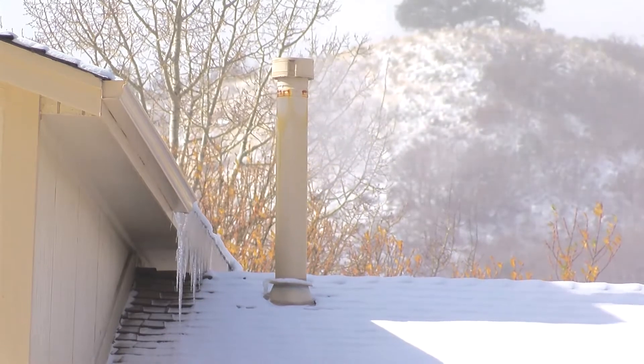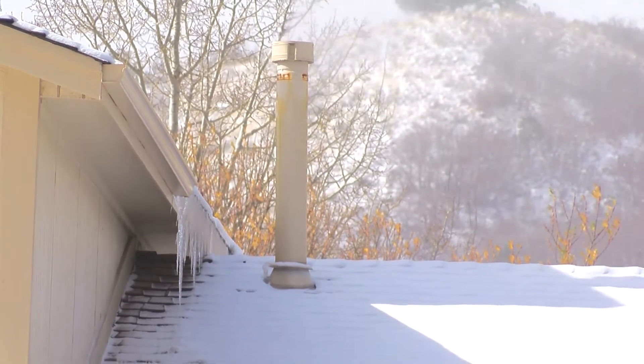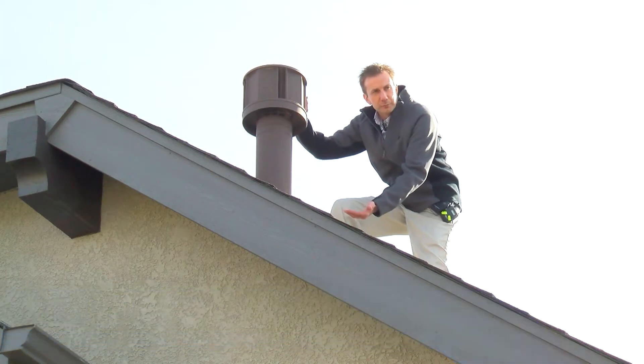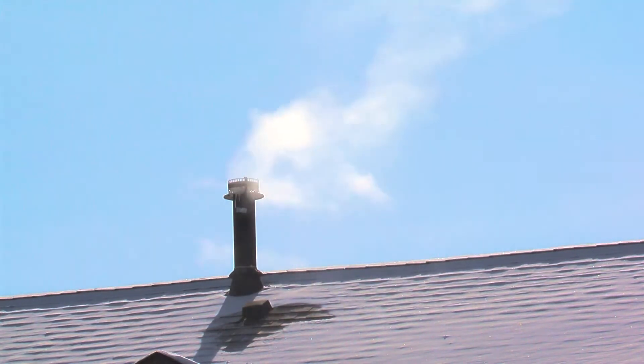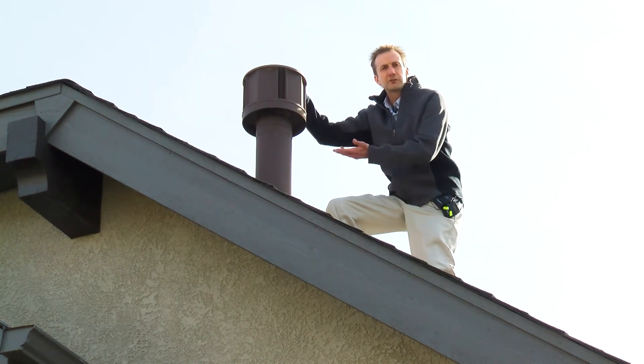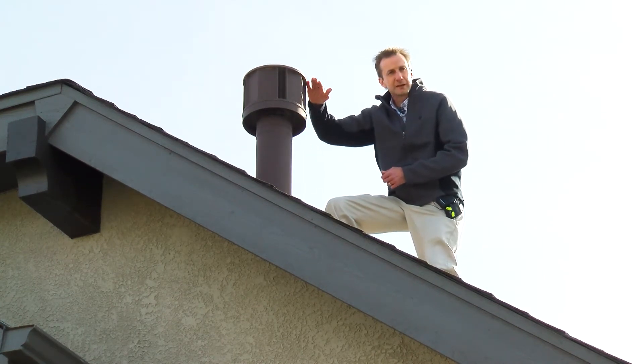At the very top on the exterior of the home, you'll have a B vent cap, which is basically a rain guard and a way to make sure that the CO and exhaust are taken to the outdoors. When shingles are being removed by the roofing contractor, if they get too close with the pitchfork, it can cause the vent to become disconnected underneath the roof itself. The disconnected vent just under the roof is one of the biggest issues we've seen — either from being too rough with it, or the cap being pushed too far down, or the hailstorm beating the cap down itself.